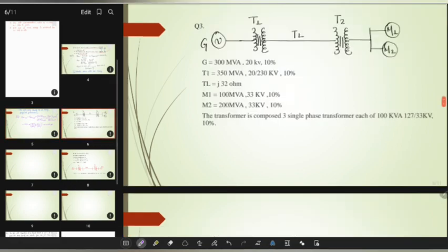Now in our next question, see, in this question all the components, generator, transformer, motor, all the components have a reactance of 10%, but it is based on the individual ratings of each component. In per unit representation, all the reactances must be referred to one common base.